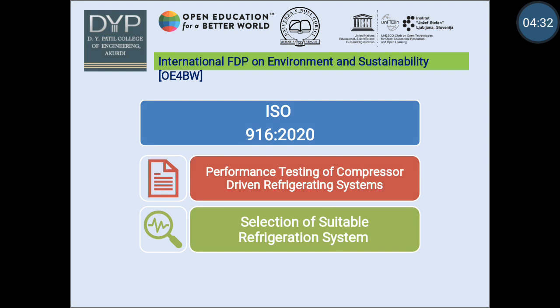The next ISO standard is ISO 916-2020. This document applies to the performance testing of compressor-driven refrigerating systems. Remember, this document does not apply to testing of other refrigeration processes such as vapor absorption process or steam jet refrigerating systems. It also covers testing of the suitability of refrigerating systems for specific uses such as household refrigerators and refrigerated commercial units based on refrigerating capacity.